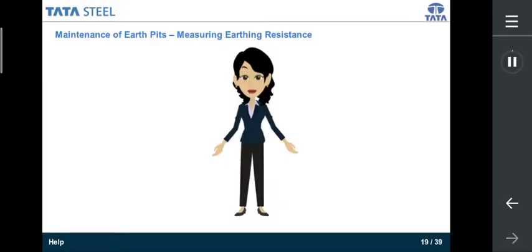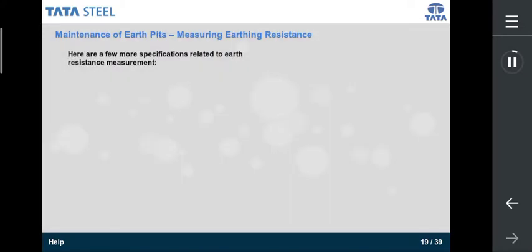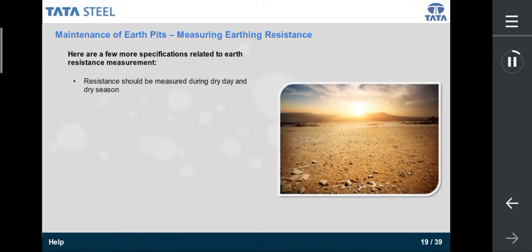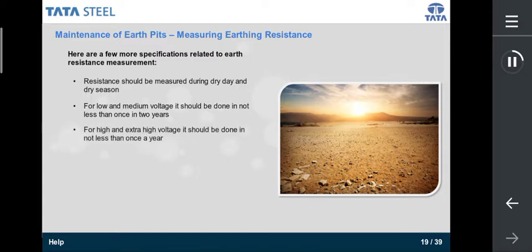So now we know that earth resistance varies from season to season. Well, let us look at a few more specifications in this context. Resistance should be measured during a dry day and dry season. For low and medium voltage, it should be done not less than once in 2 years. For high and extra high voltage, it should be done not less than once a year.